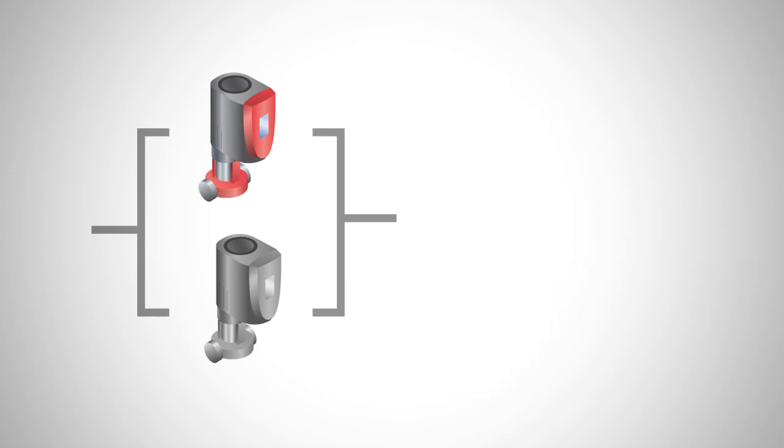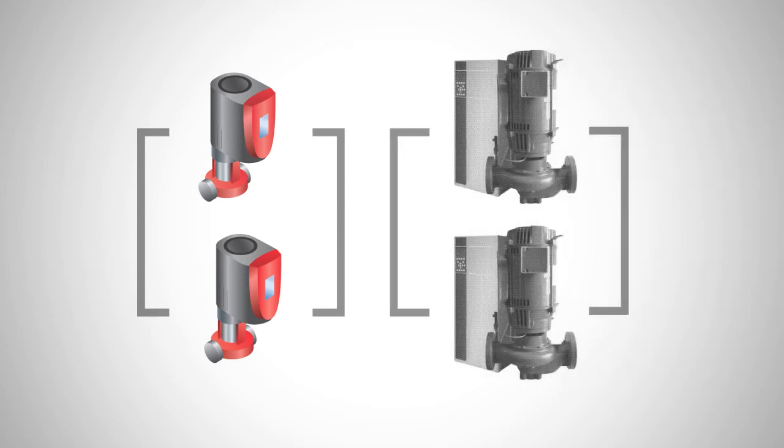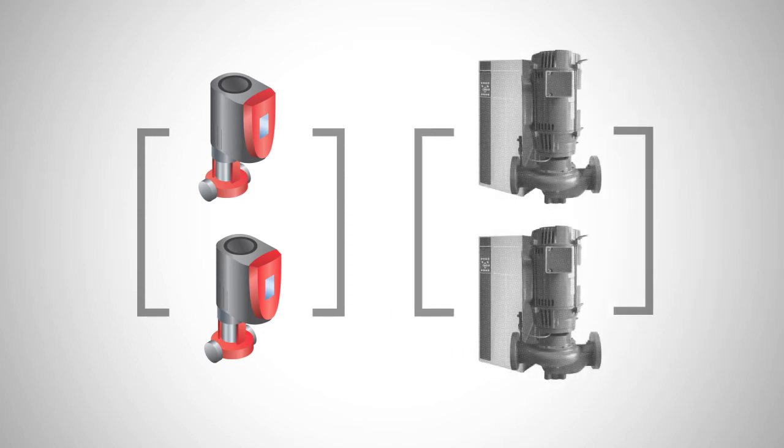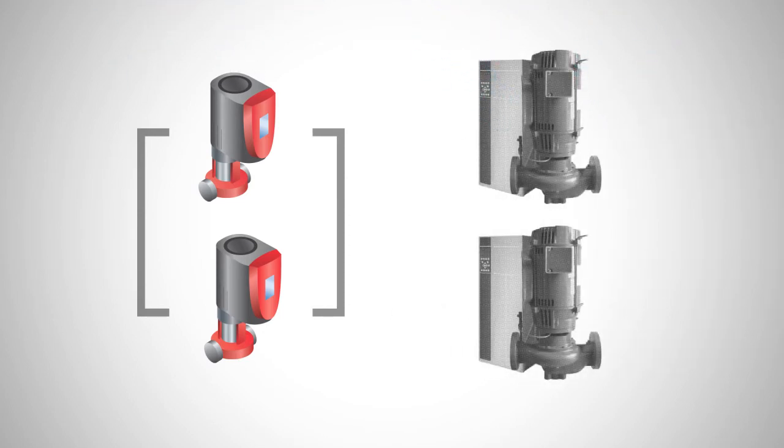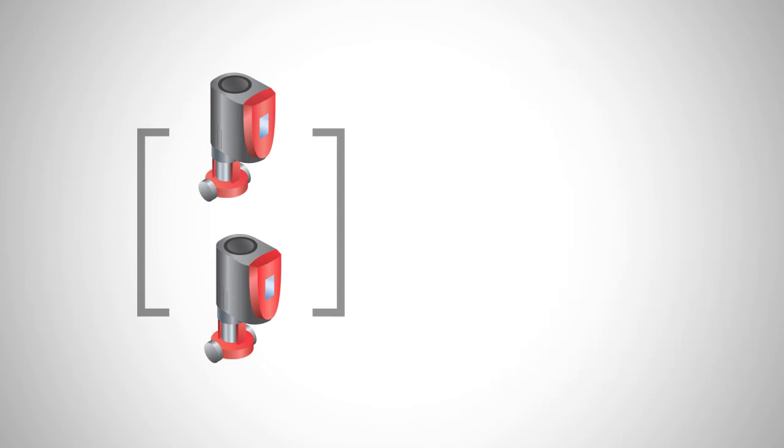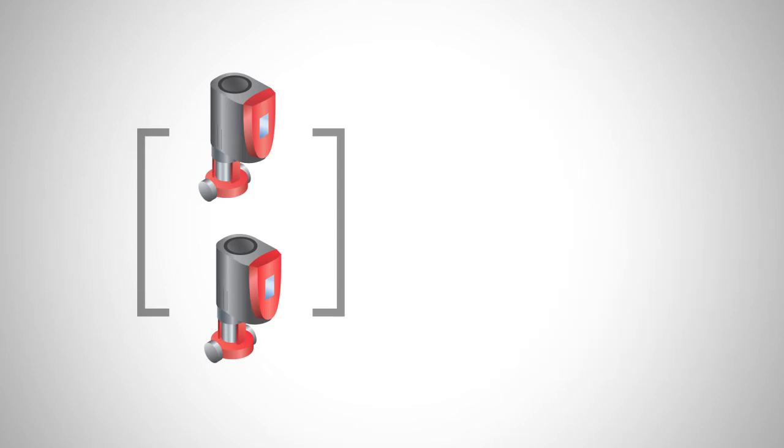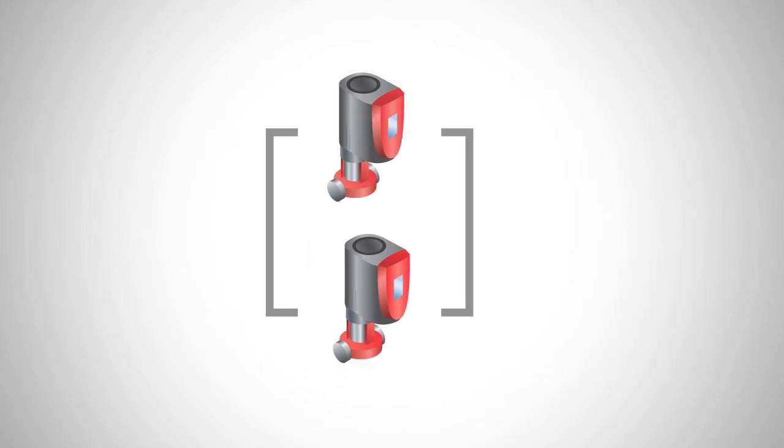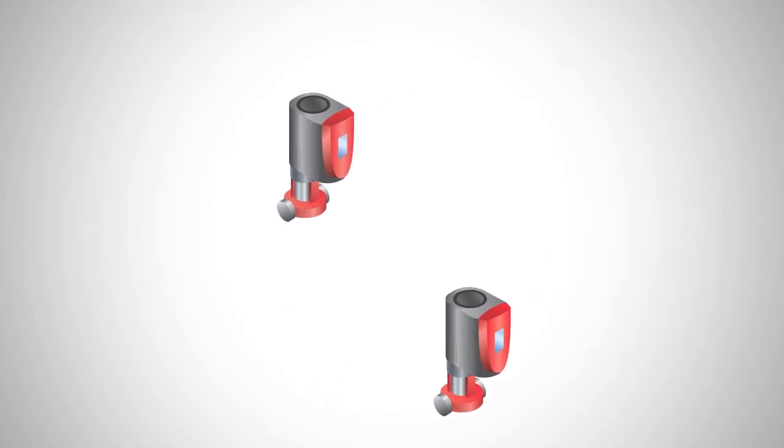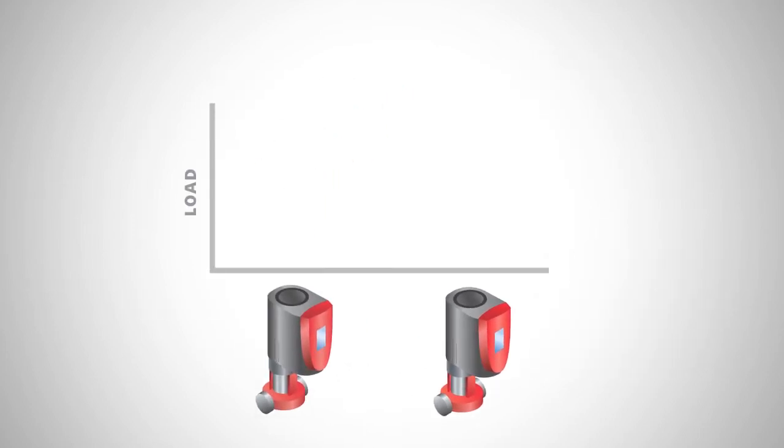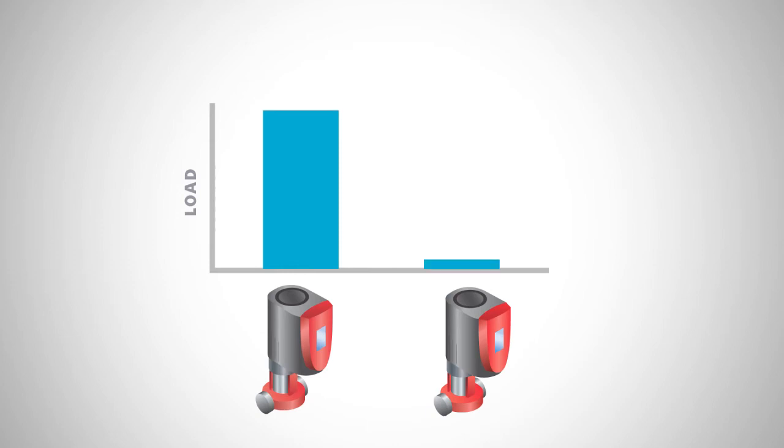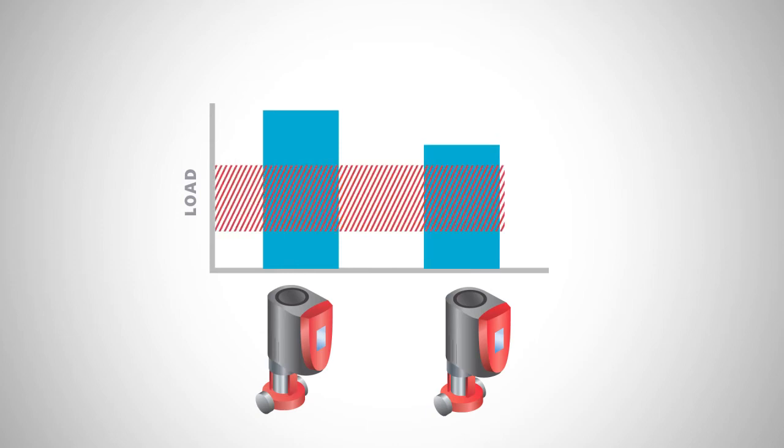Multiple smaller pumps configured in parallel are less expensive than larger pumps in the traditional duty standby configuration. Even more important, pumps installed in parallel can be staged and controlled for best efficiency across the entire pump array.